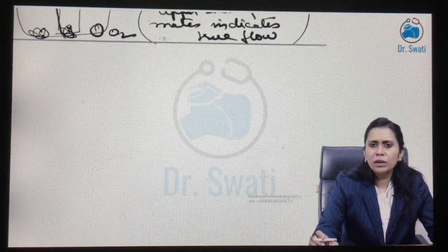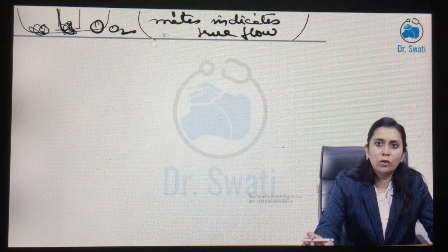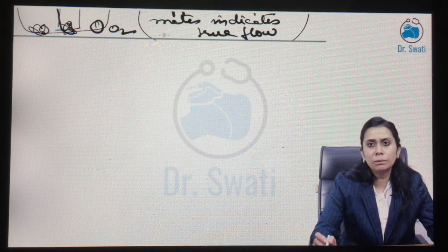Now vaporizer, I don't have to study anything with you. We just have to know about color coding, which we have already discussed in inhalational anesthetic agents. We discussed halothane as a red color vaporizer, isoflurane purple, sevoflurane yellow and desflurane blue.